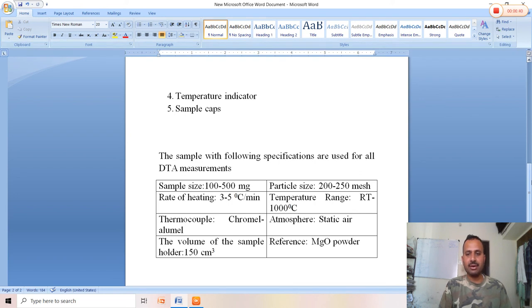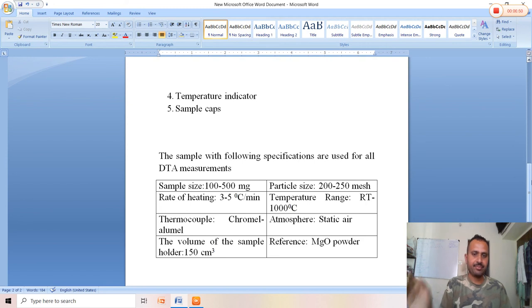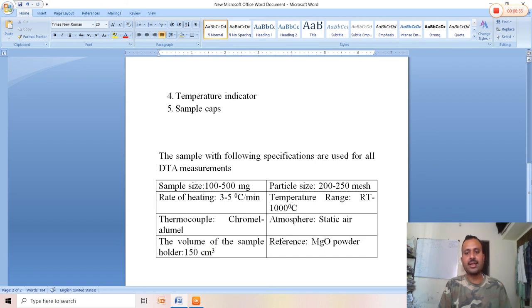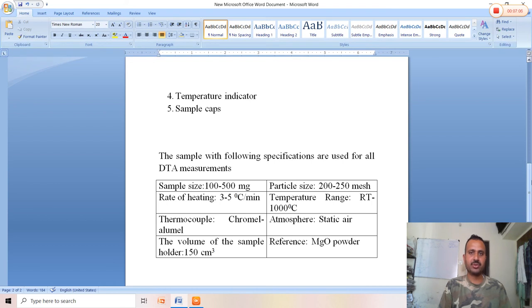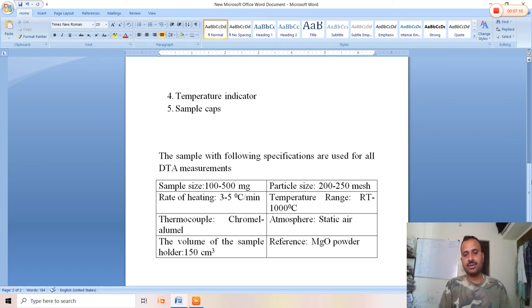The temperature range is from room temperature to 1000 degrees centigrade. A chromel-alumel thermocouple is employed, and the atmosphere should be static. The volume of the sample holder should have a capacity of 150 cubic centimeters (150 mL). Most importantly, the reference material selected for DTA analysis is magnesium oxide powder. This covers the basic principle and instrumentation of DTA.